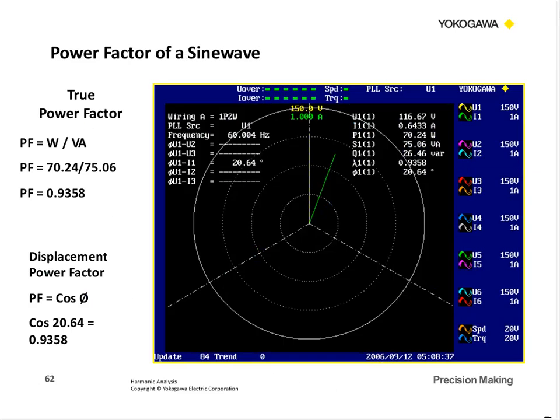If we look at the power factor on a sine wave, and this is a vector analysis done from one of our power analyzers, we look at the phase angle between the voltage and the current at 20.64 degrees. So if we take the cosine of 20.64, down here we get 0.9358. Now, if we take watts divided by VA, our wattage over here was measured at 70.24, and the VA at 75.06, so we get these measurements over here. Okay, so watts divided by VA comes out exactly the same. Now this is on a sine wave. So true power factor and displacement power factor on a sine wave obviously have to come out the same, and this just shows you how they do that.